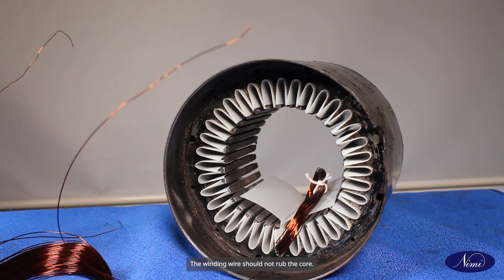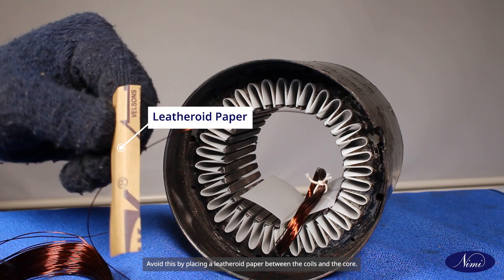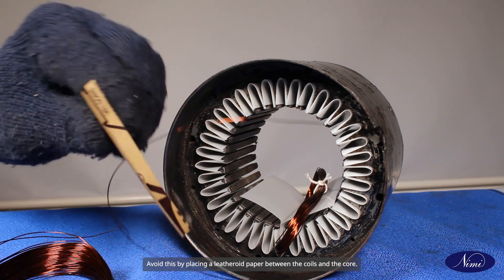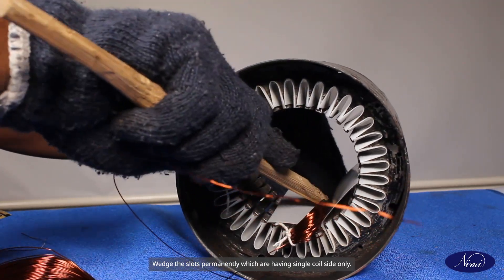The winding wire should not rub the core. Avoid this by placing a leatheroid paper between the coils and the core. Wedge the slots permanently which are having single coil side only.